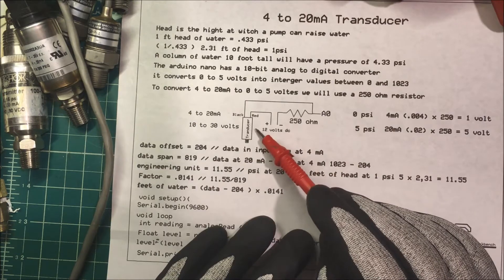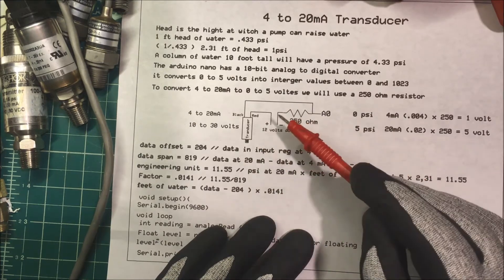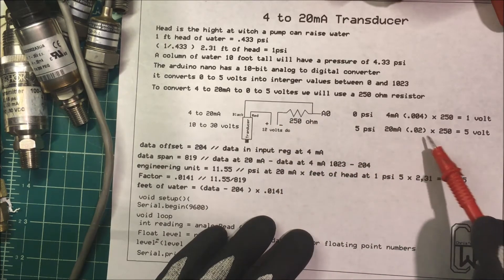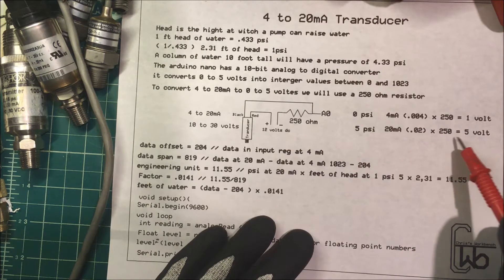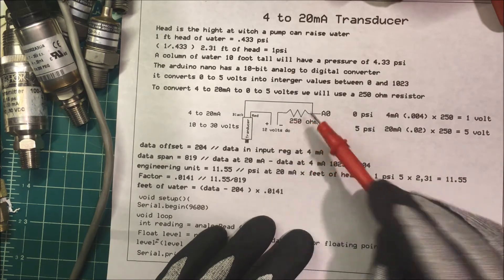Now at 5 psi my transducer is going to put out 20 milliamps. 20 milliamps times 250 ohms is going to be 5 volts. I'll be dropping 5 volts across here.